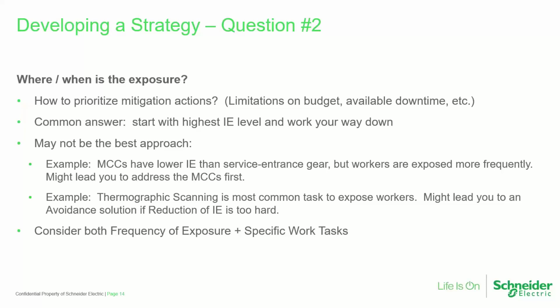I said, no, we want to look at the MCCs, the low voltage MCCs. Like, well, why? I mean, this is like 10 calories, this is 12. Well, the deal was, at those substations, they only interacted with that equipment on an infrequent basis. When they're doing their annual maintenance, or very rarely did they have to do any kind of interaction with that particular equipment. But the way the engineer at the plant explained it to me was, at the MCCs, they've got people in there on a weekly basis or even a daily basis having to reset a motor or do some troubleshooting in an MCC bucket or whatever.